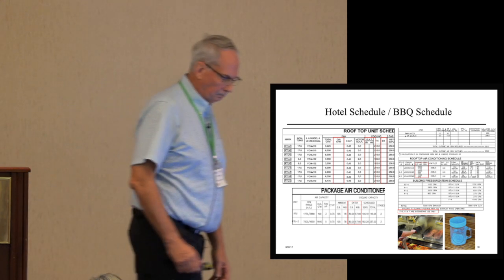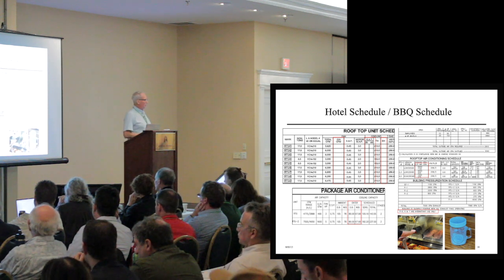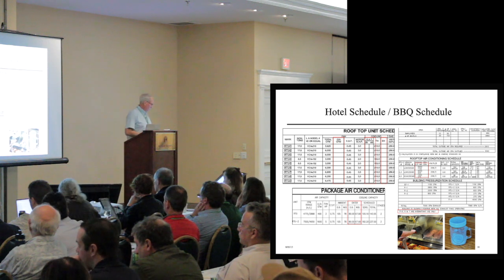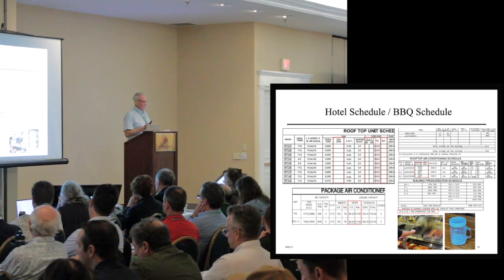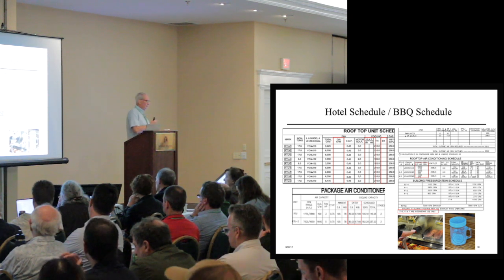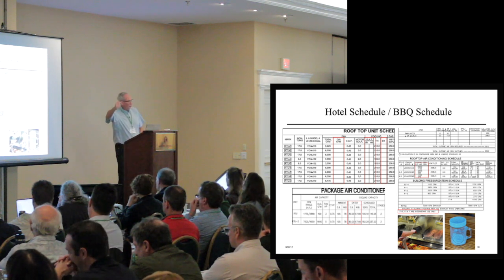Okay? So down the right-hand side is another restaurant project for that same general contractor that he called me into after it was built and after he had all kinds of problems. In the photo on the bottom left, when he called me in, it was so humid in the building, they were having two major problems that he was complaining about. Number one, the meat display case. They have to have an employee squeegee it, and by the time she gets to the other side, go to the beginning and squeegee it again.